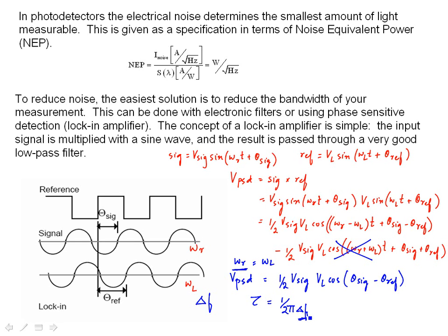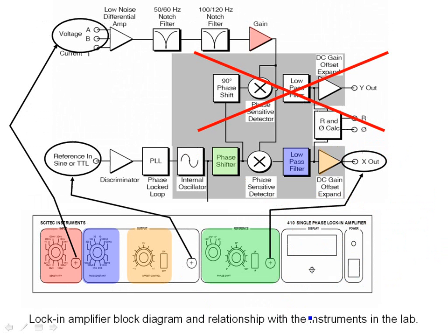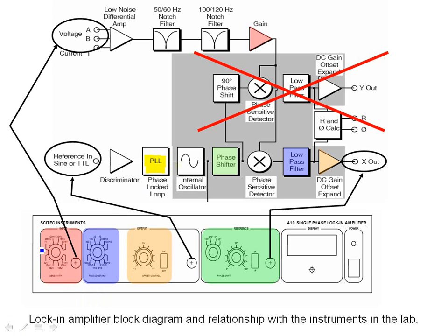Let's take a look at the block diagram of the lock-in we have in our lab, and this is a single-phase lock-in. I will be talking about what a single-phase or dual-phase lock-in is. Now, an important block in this block diagram is the PLL, and this PLL, which is the phase lock loop, it just tracks the reference phase so that theta, the phase of the signal is equal to the phase of the reference. And the phase difference can be made zero by the phase shift knob we have on the front panel.